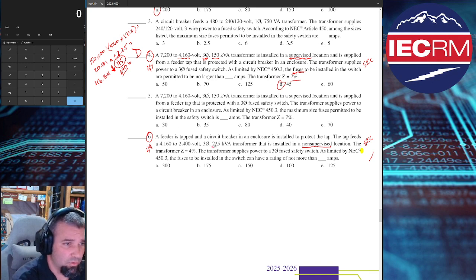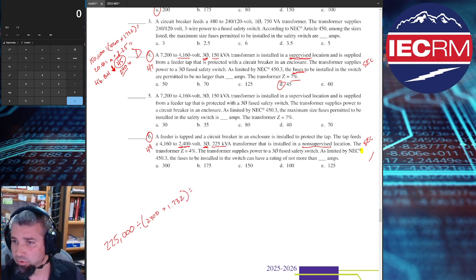All right, we've got a 225 kVA transformer. Let's write that out: 225,000. I'm going to divide that by my secondary voltage, 2400 in this case. And since I'm in 3-phase, I will use 1.732. Okay, let's punch it in. We'll start doing these faster.